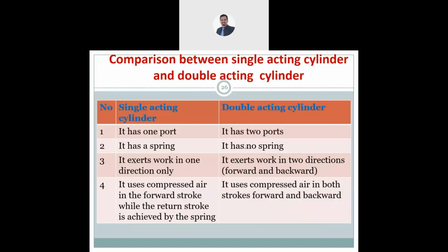Okay, so then you see the comparison. I think you are familiar with single acting cylinder and also double acting cylinder. So I think you pun dah buat lab. Okay, so single acting cylinder always with spring and double acting cylinder without spring. You boleh tengok single acting ada one port, double acting ada dua port, and it's only doing work in one side. The return is based on spring, mechanical. Tapi untuk double acting cylinder, both way kalau you nak extend ataupun retract, you need to use compressor.